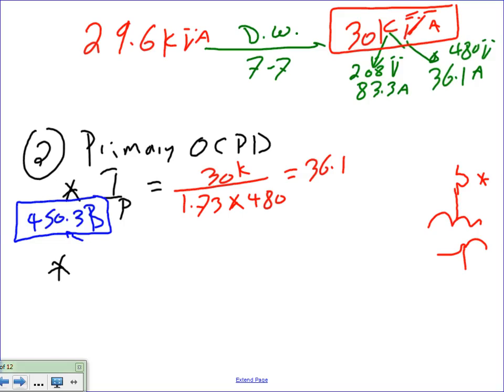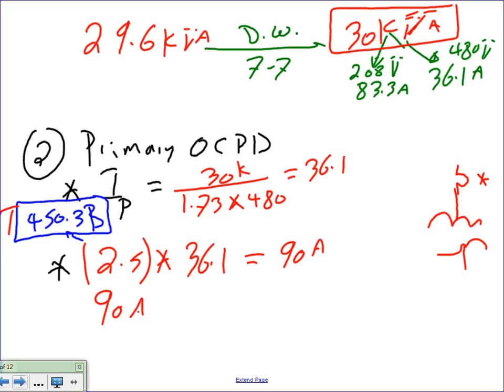Now, Chris, if you go to Table 450.3(B) for any transformer, it will tell you that your multiplier is going to be 2.5 multiplied by the full load current, which is 36.1, and I would have 90 amps. Then you take your 90 amps into 240.6, and we hit the jackpot, 90 amps.